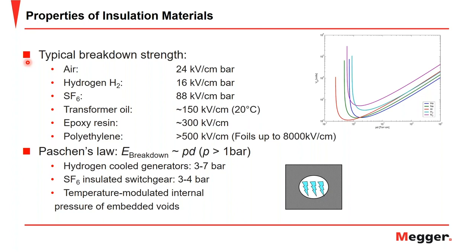And nitrogen is an electropositive gas, which makes it a poor insulator due to its availability of free electrons. But other gases, such as hydrogen or SF6, can be really good insulators when used in compressed forms, such as GIS or GIL. For instance, the breakdown strength of SF6 at 4 bar is roughly 3 times higher than at 1 bar.